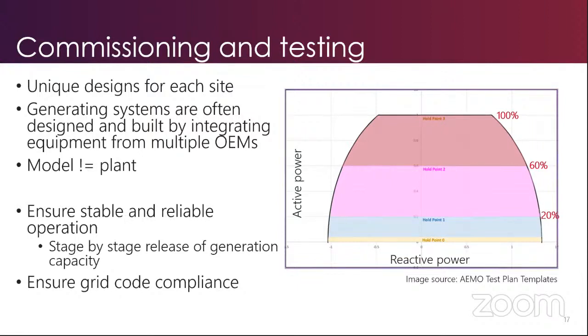So what we typically do is, stage by stage, we release the capacity as shown in the figure on the right-hand side of the slide. While doing that, at each stage, we ensure grid code compliance, meaning there are certain tests that can be done to verify compliance, and then we release stage by stage. So the operator gets the confidence that this plant will meet the grid code as well.